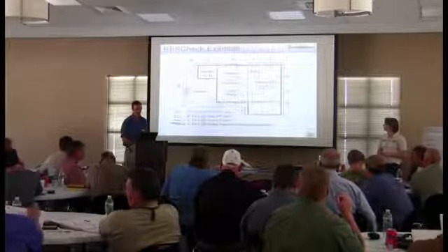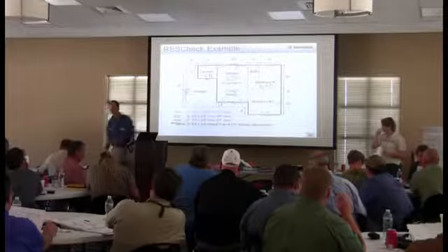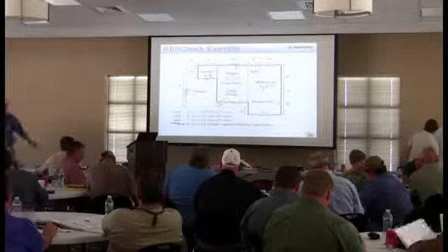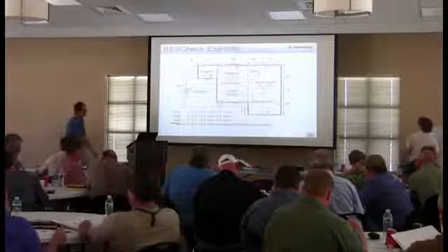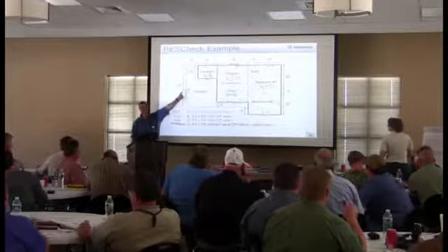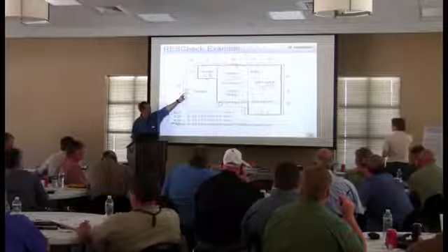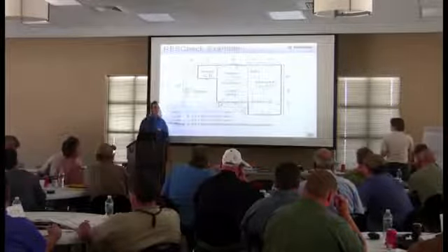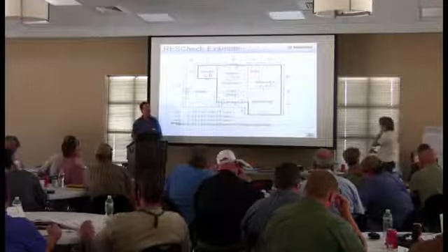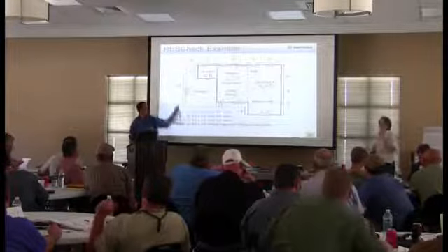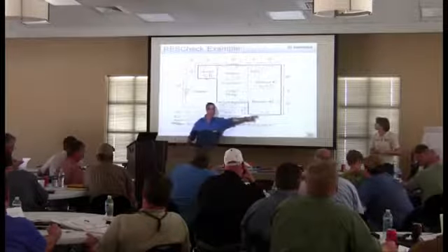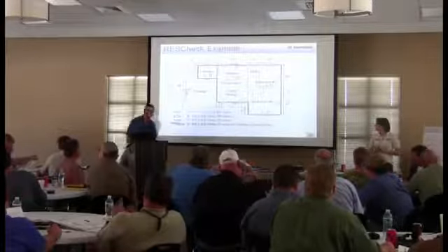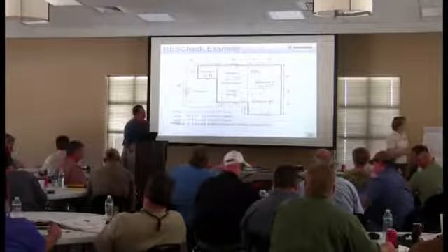So everybody see how we got 7 of the A windows to count, and the one in the garage is not part of the envelope. So we don't care. That window over here, could that be a single pane window? Absolutely. Hopefully the builder is going to spec the same window everywhere, because otherwise Murphy's Law will take over and the single pane window will end up like here or something, in the wrong place. But technically it doesn't matter. It's not part of the envelope. All right, 7 windows that are A.